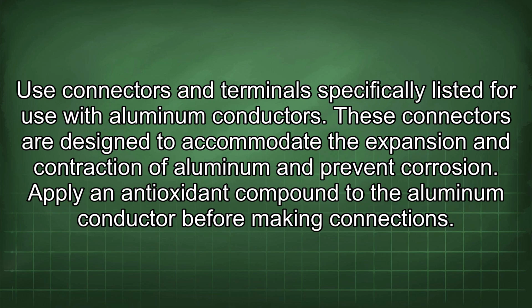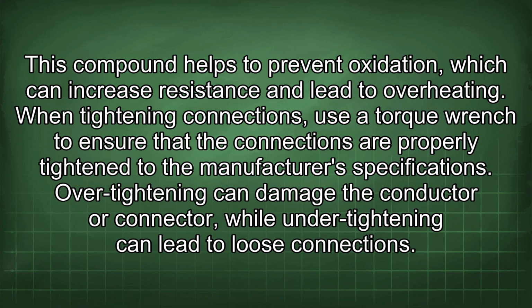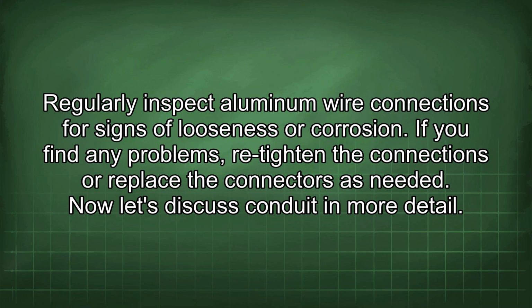Apply an antioxidant compound to the aluminum conductor before making connections. This compound helps to prevent oxidation, which can increase resistance and lead to overheating. When tightening connections, use a torque wrench to ensure that the connections are properly tightened to the manufacturer's specifications. Over-tightening can damage the conductor or connector, while under-tightening can lead to loose connections. Regularly inspect aluminum wire connections for signs of looseness or corrosion. If you find any problems, retighten the connections or replace the connectors as needed.